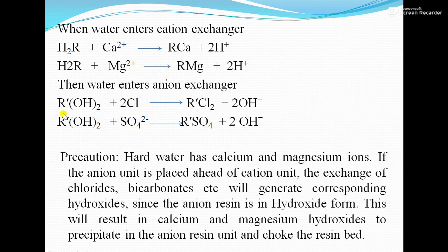Similarly, anions get exchanged in the second compartment. The OH⁻ in R(OH)₂ is replaced by Cl⁻, and similarly OH⁻ is replaced by SO₄²⁻, giving R(SO₄). Precaution: if the anion unit is placed ahead of the cation unit, the exchange of chlorides, bicarbonates, etc. will generate corresponding hydroxides. Since the anion resin is in hydroxide form, this will result in calcium and magnesium hydroxide precipitates in the anion resin unit, choking the bed.